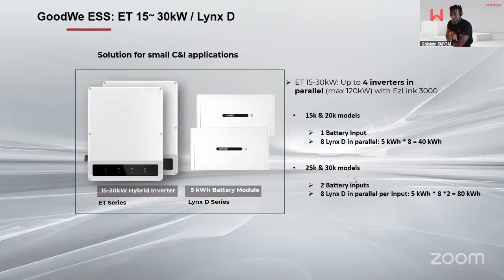So again, with the smaller subset, 15 to 20 kilowatt, the maximum battery can get to 40 kilowatt hours per inverter. Of course, you can multiply it by 4, for 120 kilowatt hours, because 4 inverters can be put in parallel with the EZLink 3000. And for the bigger platform, 25 and 30 kilowatt, 80 kilowatt hours of storage per inverter of maximum 30 kilowatt, that can then be multiplied by 4 with the EZLink 3000.